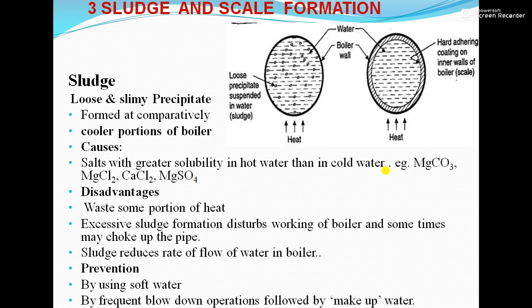What are the disadvantages of sludge? First, due to the presence of sludge, we have to heat water more to generate the required steam, meaning there is wastage of heat. Second, excessive sludge formation disturbs the working of the boiler and sometimes it may choke up the pipe. Third, sludge reduces the flow rate of water in the boiler.